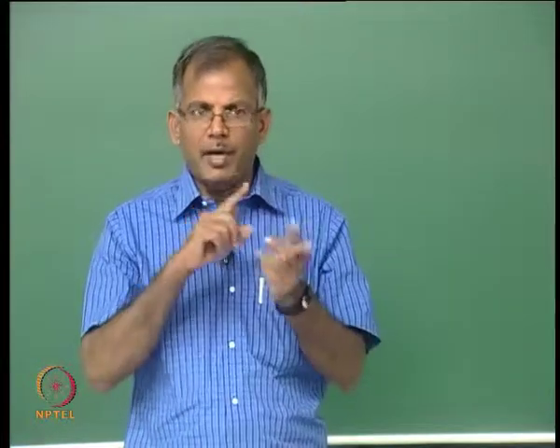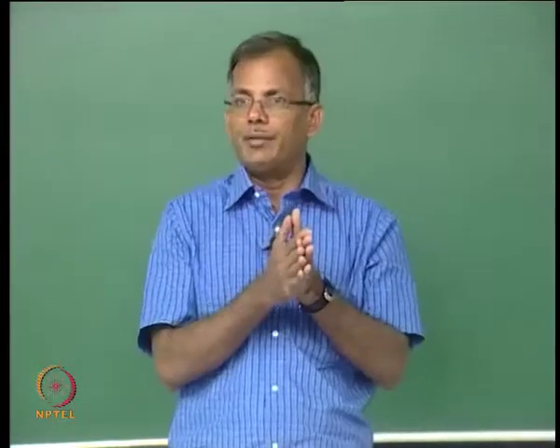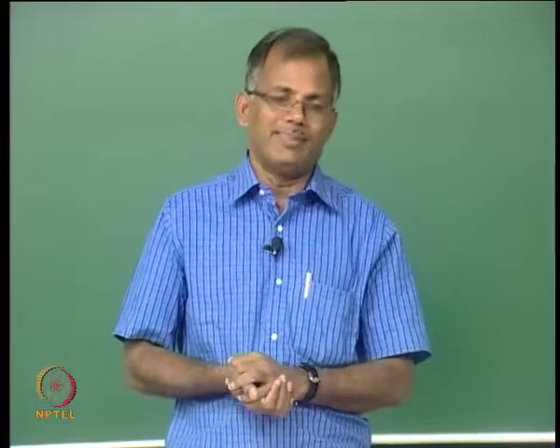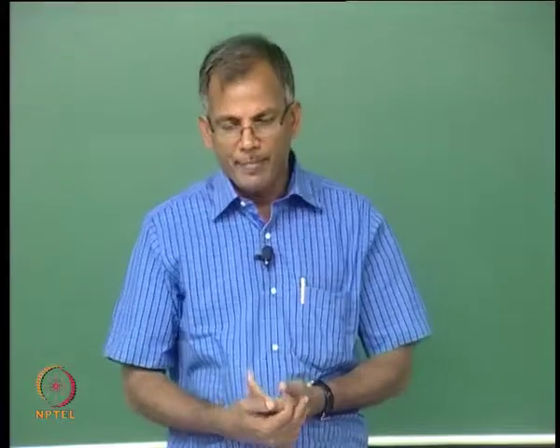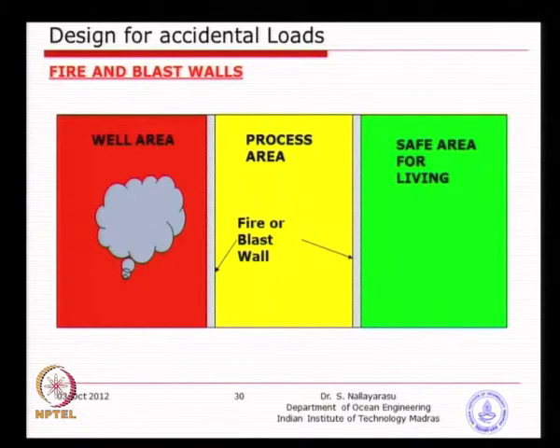Sometimes you combine the fire and blast wall together — a firewall that can take a certain amount of loading, which is a combined effect. One is a structural requirement; the other is performance with regard to temperature. The external temperature needs to be reduced to a certain level inside the building. If there is a fire at 900 degrees, the insulating material must not conduct that temperature to the other side above a defined limit. The same wall can be designed for a certain pressure due to blast — it is a combined fire and blast wall.